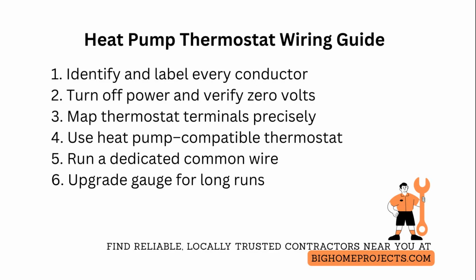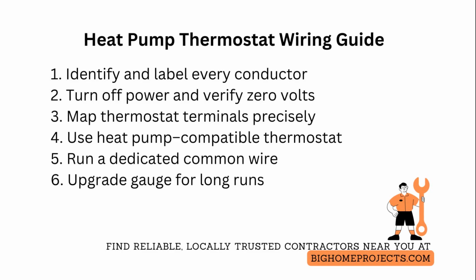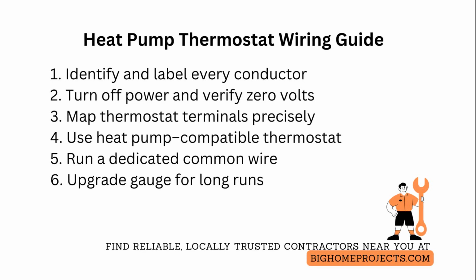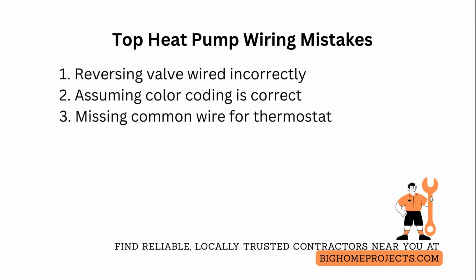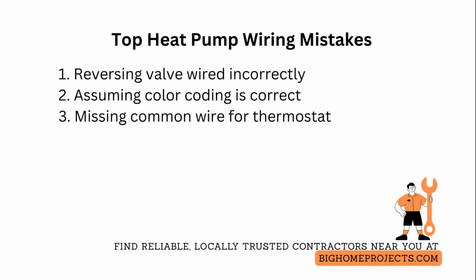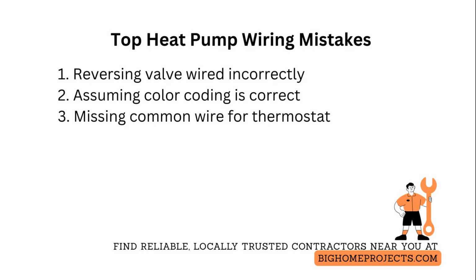When in doubt, consult the outdoor unit wiring diagram and the indoor control board schematic. And if the system uses manufacturer proprietary communication, use the manufacturer-approved thermostat or an interface adapter rather than forcing a generic unit. One of the most frequent thermostat wiring mistakes is misidentifying the changeover or reversing valve wire, which causes heating and cooling to run opposite.